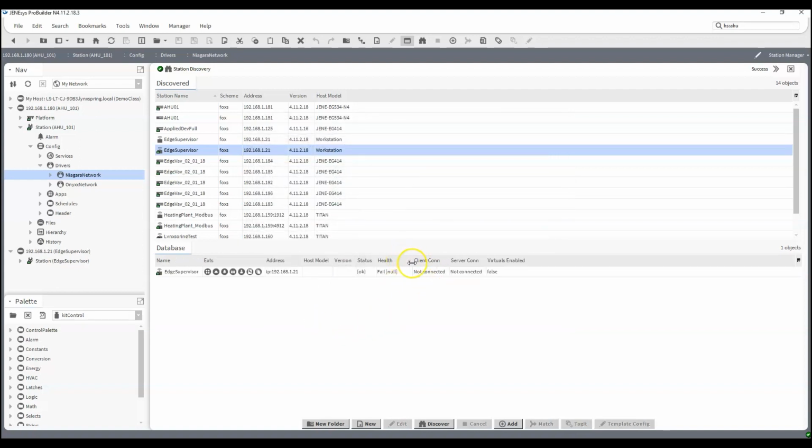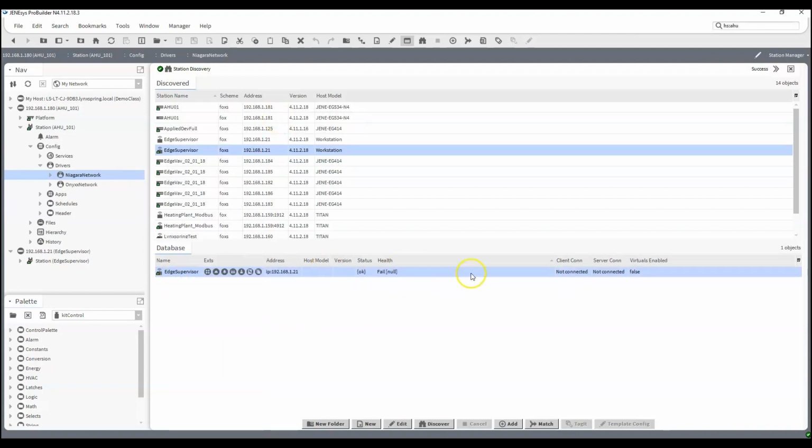It's always going to fail the very first time. If I ping this, I'm going to get a certificate error. In this case, it's org.bouncycastle.tls. When you see this, you know this means that the certificate has not been approved. Because this is a secure connection and it works with certificates, they need to be approved in order for a station to communicate to another station.